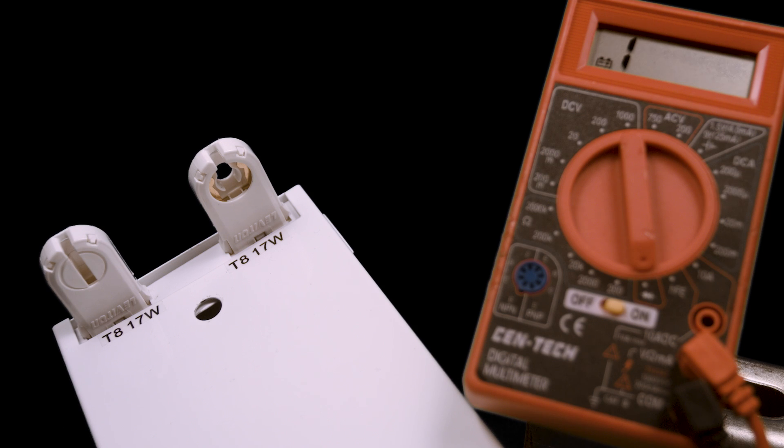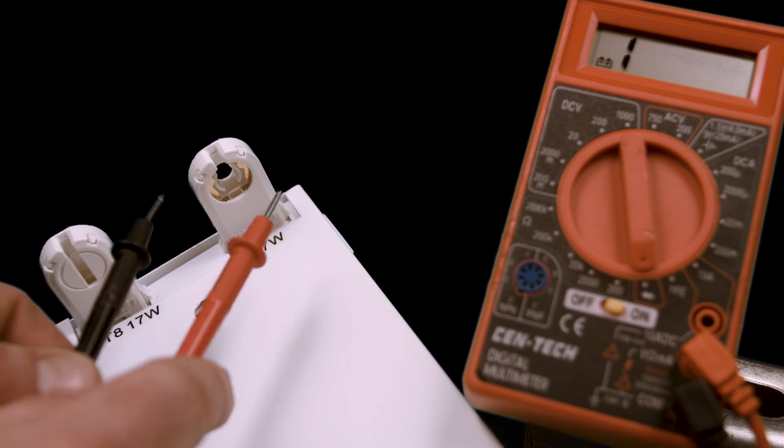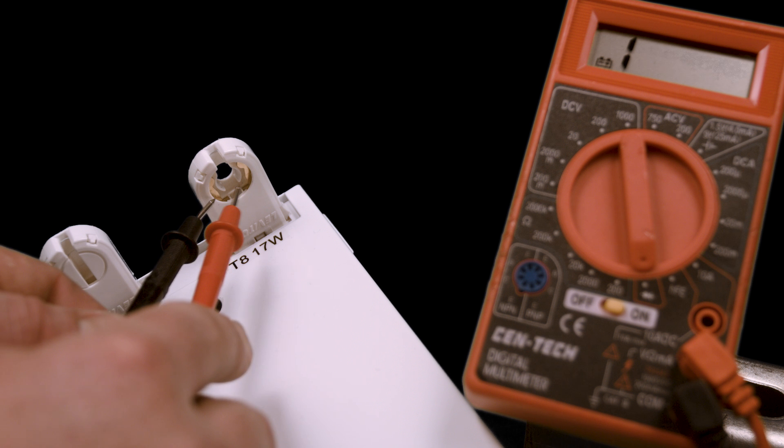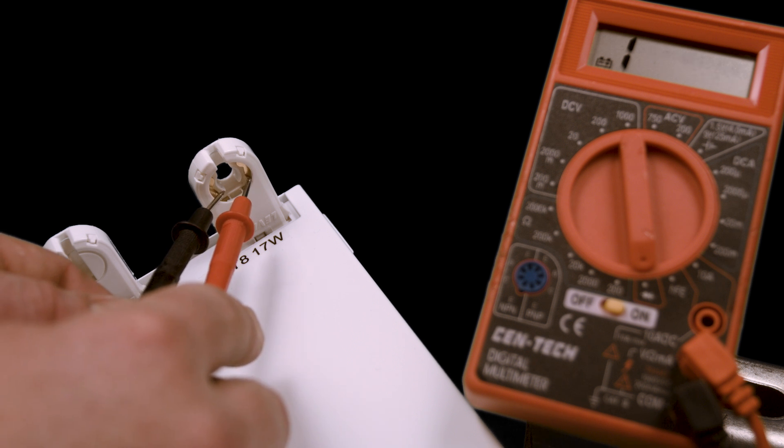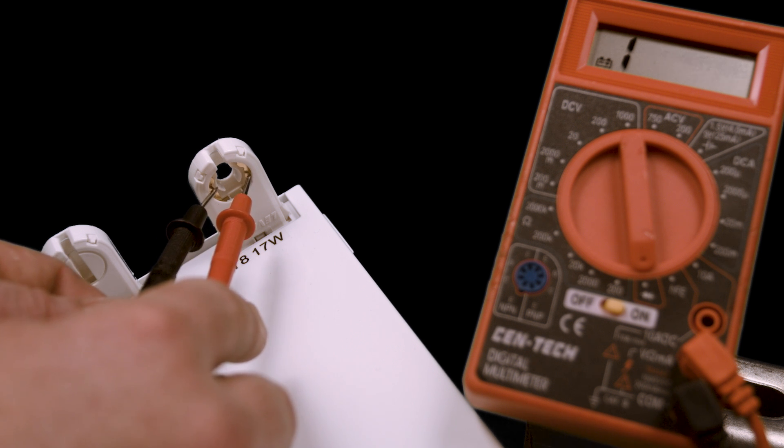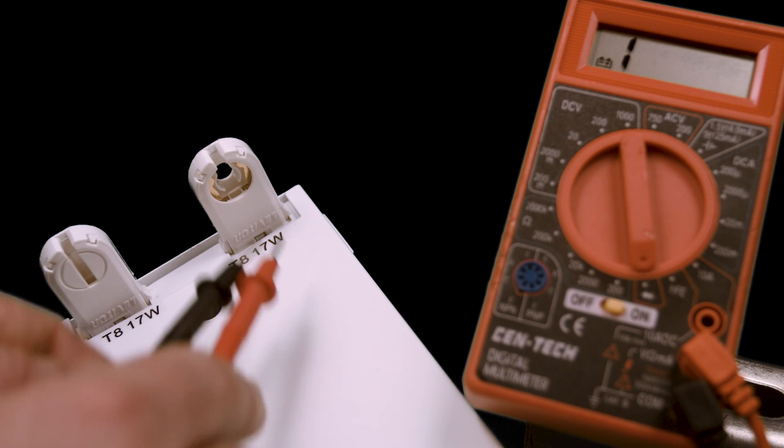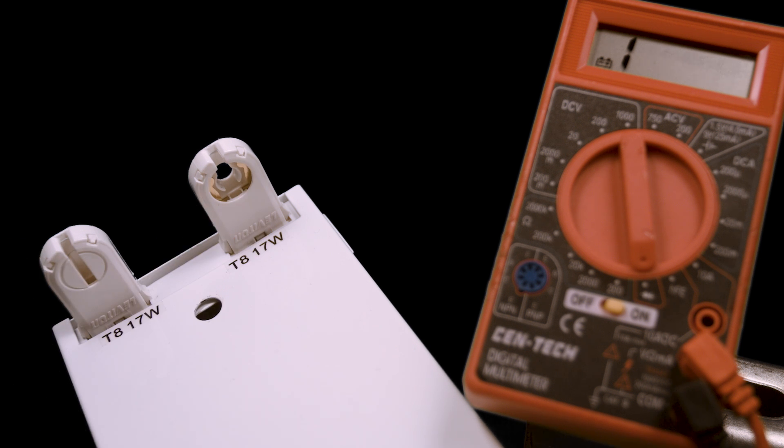Now, let's test the non-shunted socket again. Touch the multimeter probes to the contacts where the pins go. The display does not change, indicating that the circuit is broken or separated. These contacts are not joined, confirming that the socket is non-shunted.